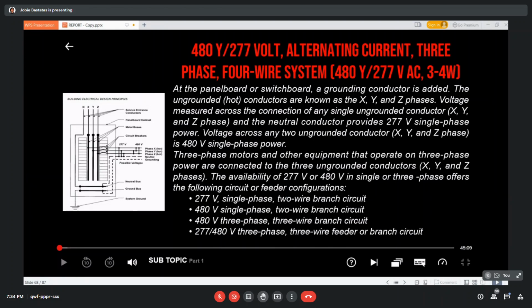At the panel boards or switchboard, a grounding conductor is added. The ungrounded hot conductors are known as the X, Y, and Z phases. Voltage measured across any single ungrounded conductor and the neutral conductor provides 277 volt single phase. Three-phase motors and other equipment that operate on three-phase power are connected to the three ungrounded conductors, X, Y, and Z phases.